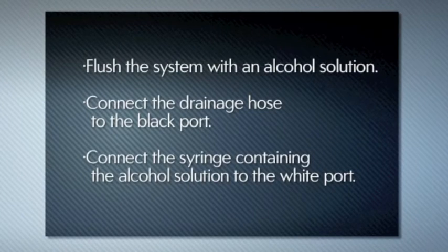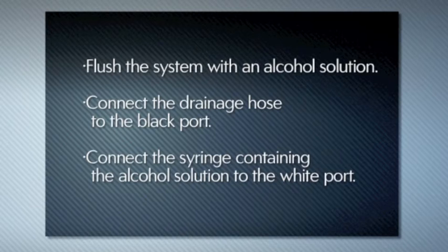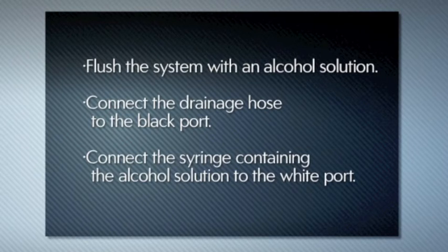When a session is complete, it is recommended that you flush the system with an alcohol solution, making sure to connect the drainage hose to the black port and the syringe containing the alcohol solution to the white port during the flushing procedure.